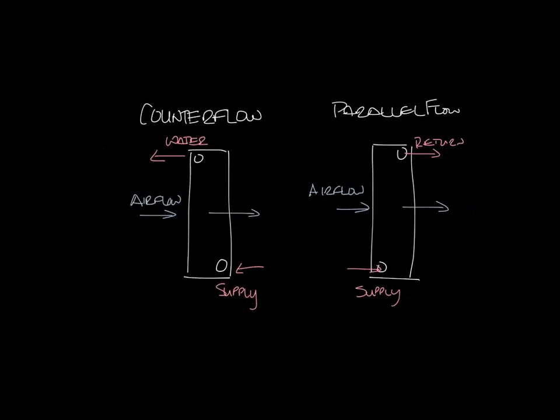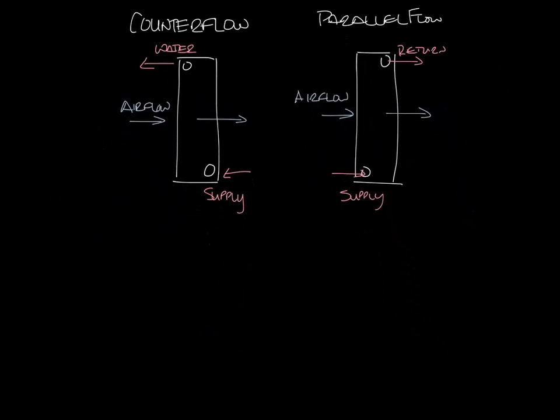One potential issue with parallel flow coils is the large temperature differential between the air and water temperatures. This can cause thermal stress on the material in the coil, and that could result in failures, in material failures over time.